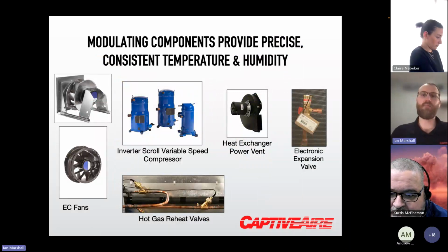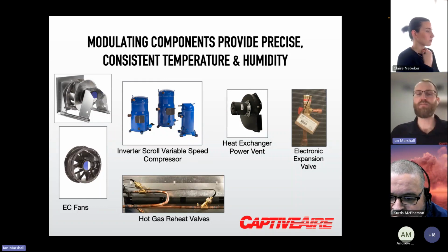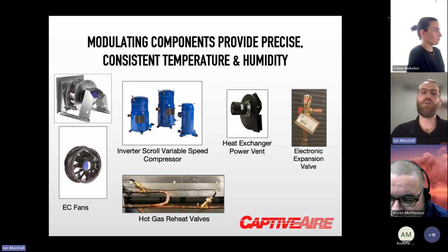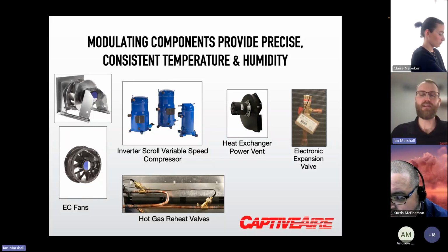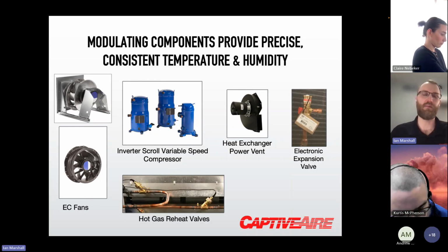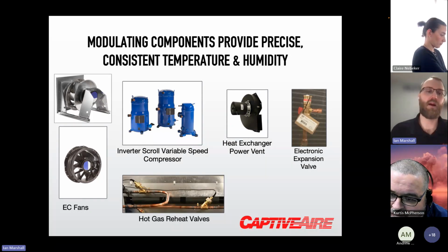So with some of the components that we utilize, we standardize across the board in our DOAS unit with what we would define as high efficiency or variable speed, fully modulating type components. So where a lot of our competition might have a low efficiency, high efficiency option, we would be standardizing in what would be defined as the high efficiency or HE option with all of our components, and that's standard on all selections. So all of our fan blower options are all direct drive. We don't have any belt driven fans in the unit. For the supply blower, it's a direct drive ECM or direct drive with VFD.